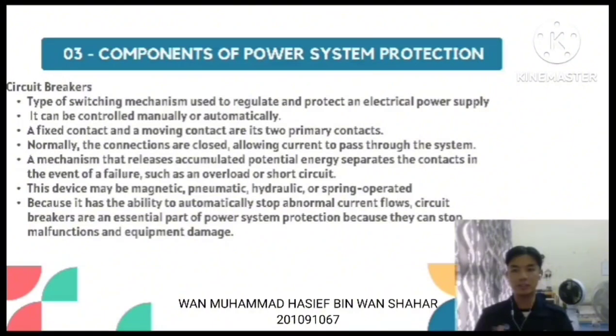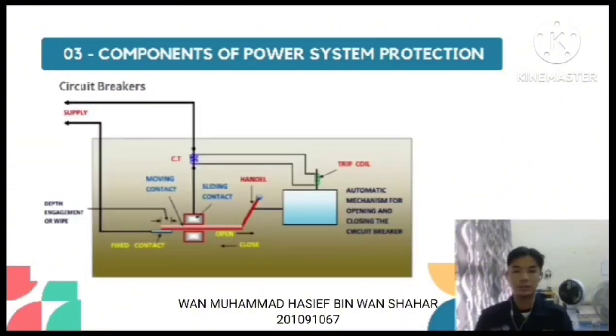A mechanism that releases accumulated potential energy separates the contacts in the event of a failure, such as an overload or short circuit. This device may be magnetic, hydraulic, or spring operated. Because it has the ability to automatically stop abnormal current flow, circuit breakers are an essential part of power system protection because they can stop malfunctions and equipment damage. This is the figure for the circuit breakers.